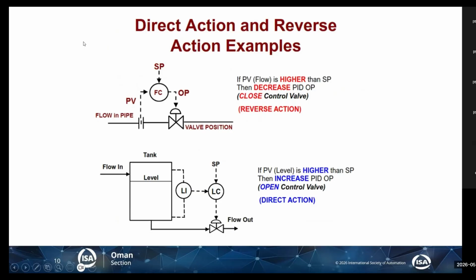Then there is other terminology that's important also: a direct action and a reverse action valve or controller. As mentioned here, if PV flow is higher than SP, decrease PID OP. So if flow increased more than the set point, I will close the valve. The valve will be closed. This is a reverse action controller. Flow increased, valve will decrease. This is a reverse action controller.